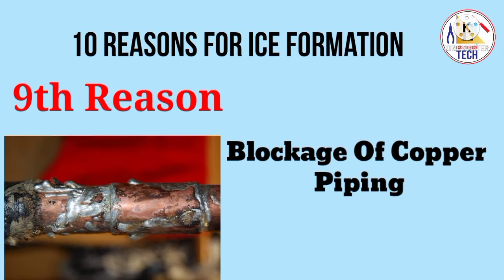Reason number nine is blockage of the copper piping. If one of the copper pipes is half blocked, at that time you will also get ice formation in the indoor unit. Check all ten reasons and you will find the solution for ice formation in your indoor unit.